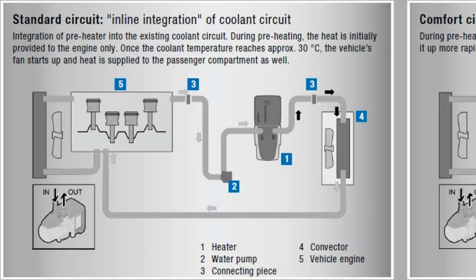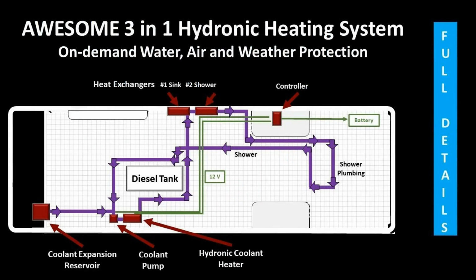When the temperature reaches 85 degrees Celsius, fuel stops flowing into the chamber, as well as air, and the device goes into standby mode, where only the water pump works. If the temperature drops below 75 degrees Celsius, the sensor reacts and restarts the heater.